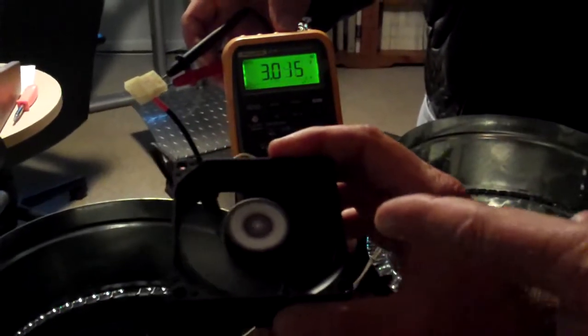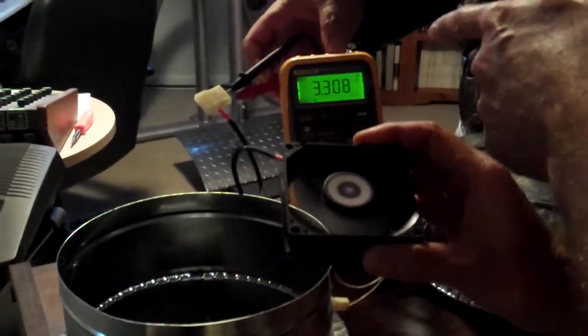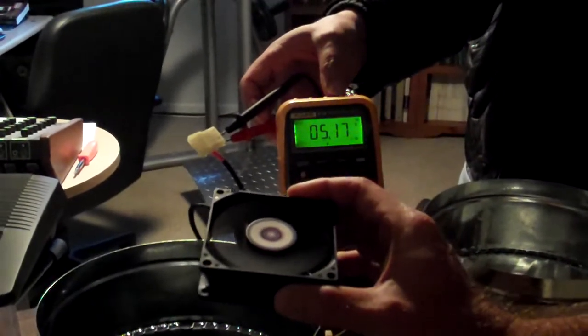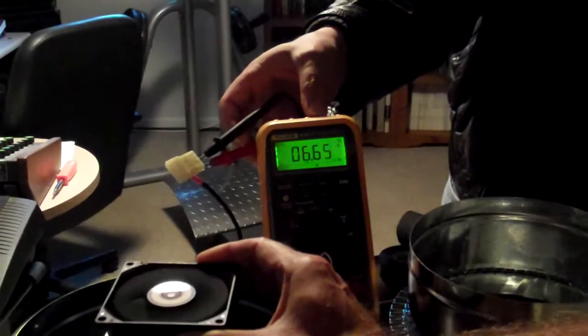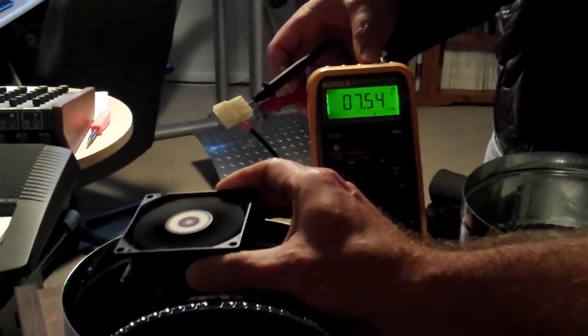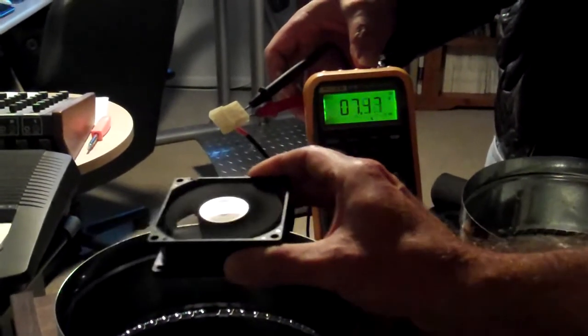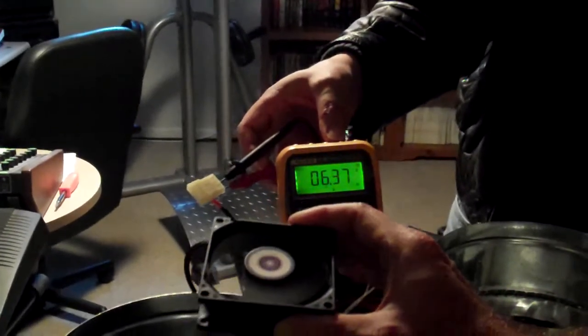You can see this fan's off to the side. Obviously we've got a lot of air blowing through this, but this is off to the side reading about 3.3 volts. And then as I move it to the center, it measures the input — and it's up to about 7.4, 7.5 volts. As the air decreases, the voltage decreases.